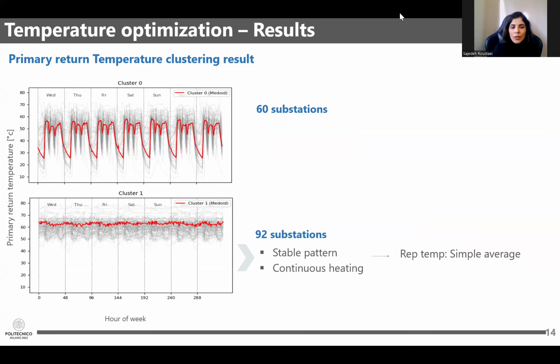So we came up with different strategies. First, using signal analysis, we started to identify the peaks happening at each profile of the substation, and then we remove them from the data of that substation because they are not the typical behavior of the users, just a result of the shutdown. Then, through percentile averaging, we started to only count the time when the heating device is actually working.